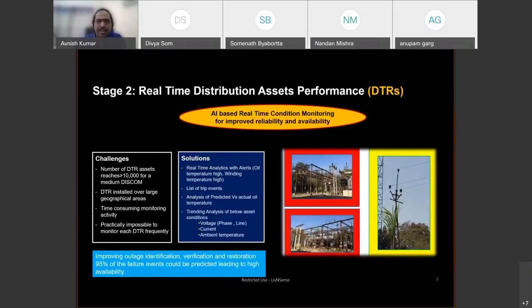Coming to distribution asset performance, the key asset is the distribution transformer and power transformer, which we are also addressing. One key challenge is that DTR assets for a medium level discom number more than 10,000. It is practically impossible with limited manpower to manage maintenance and inspection of all this, which is why there are frequent failures, identified only after they happen. The official failure rate figure reported today is almost 10%, but in my view it is more than 20%.